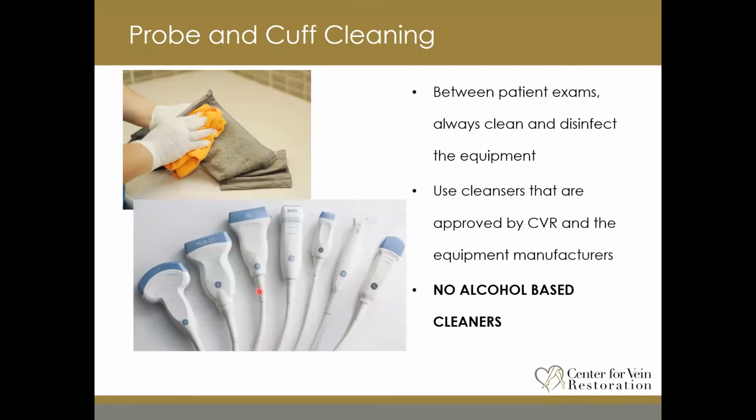Taking care of the probes is another key thing. You're utilizing the ultrasound probe. If you're in a procedure, your technologist is not there with you, somebody's not there to manage that probe for you, make sure you're not just tossing that probe. These probes have crystals in them.